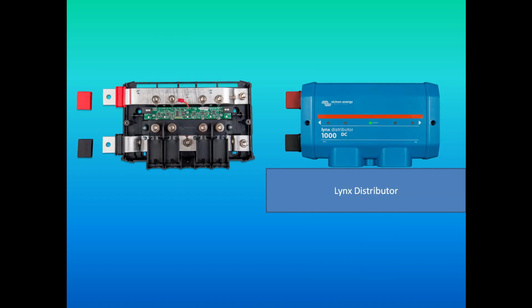This here's the Lynx distributor. I talked about putting in fuses and stuff — this Lynx distributor lets us put our negative lines on the bottom bar where the black tip is. Right above it you'll see four studs that don't go all the way up to the red bar, because we're supposed to put ANL 100 amp fuses in, or whatever fusing we need. This acts as both a positive and negative fuse bar and bus bar, so we're tackling two things at once while providing some safety, so we're not overloading or having anything draw too much power.